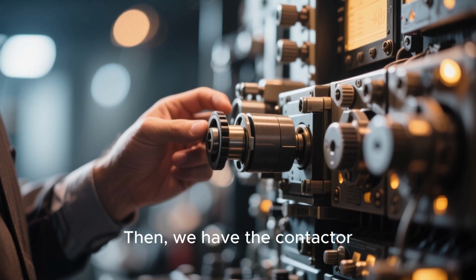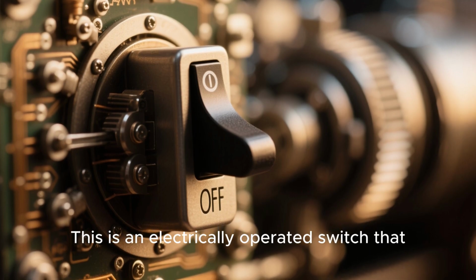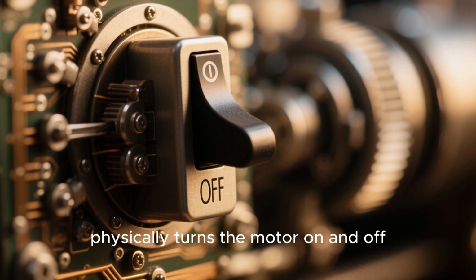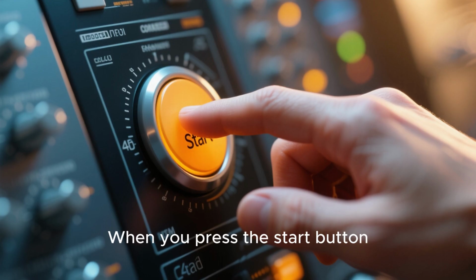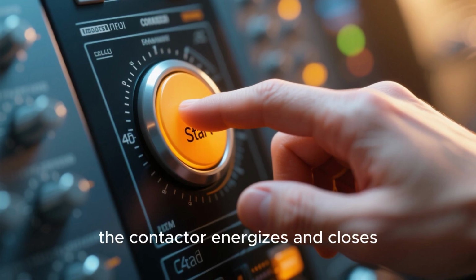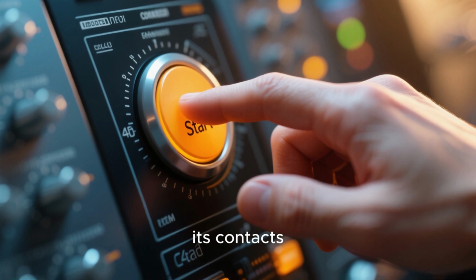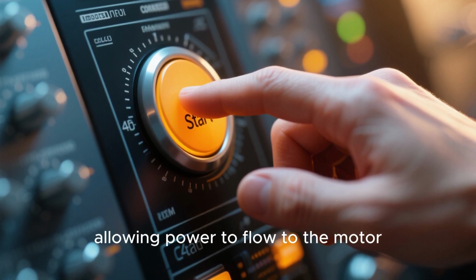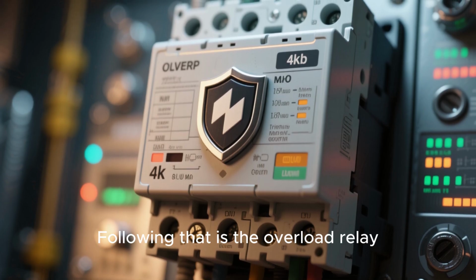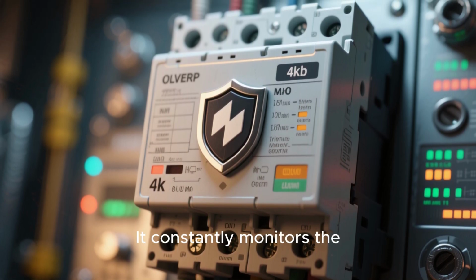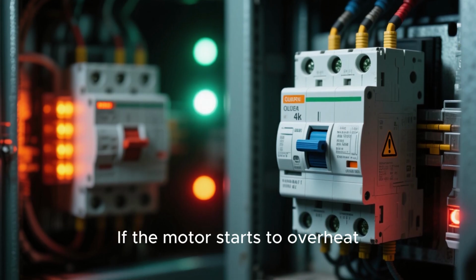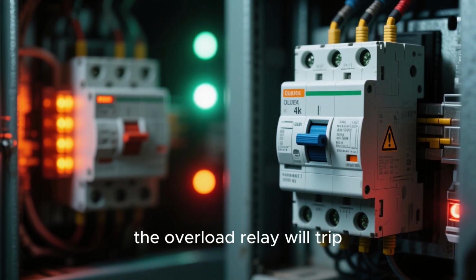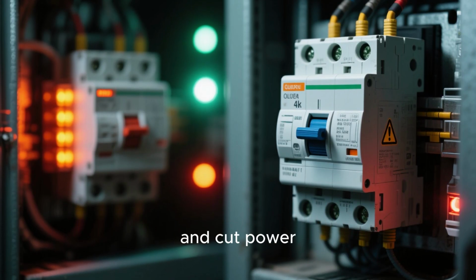Then, we have the contactor. This is an electrically operated switch that physically turns the motor on and off. When you press the start button, the contactor energizes and closes its contacts, allowing power to flow to the motor. Following that is the overload relay. This is the motor's personal bodyguard. It constantly monitors the current the motor is drawing. If the motor starts to overheat or work too hard, the overload relay will trip and cut power, saving the motor from damage.